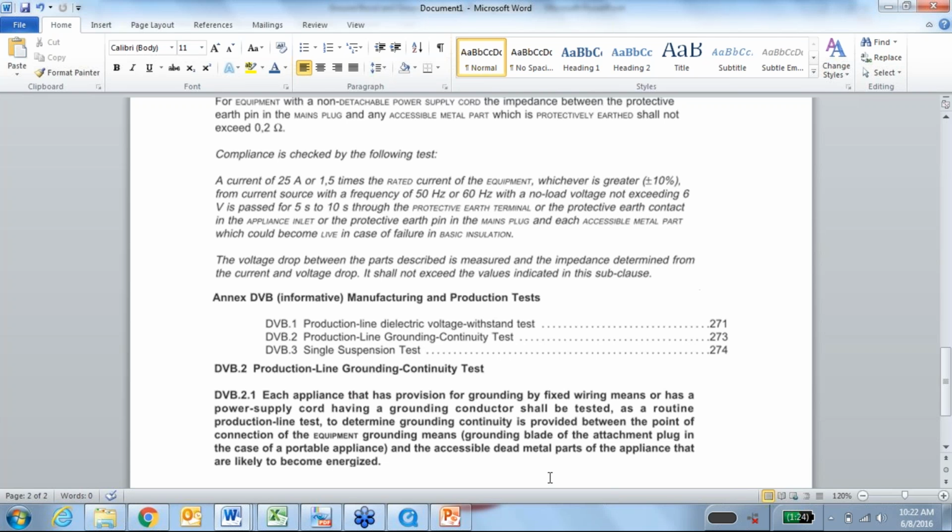But as I was kind of hinting to earlier, we're noticing that this is quickly becoming a trend, because running a ground bond test, you're kind of killing two birds with one stone. It's the same as running a continuity test. If you're passing your ground bond test, then you have peace of mind that there's continuity in ground.